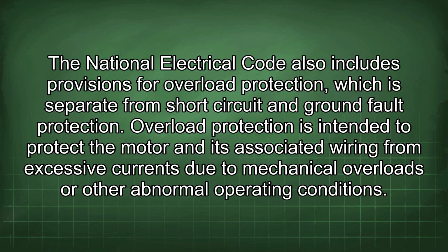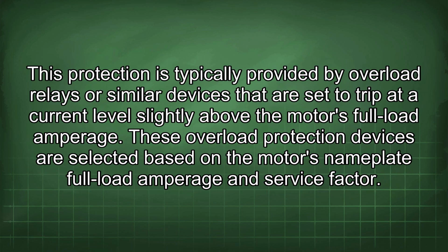The National Electrical Code also includes provisions for overload protection, which is separate from short circuit and ground fault protection. Overload protection is intended to protect the motor and its associated wiring from excessive currents due to mechanical overloads or other abnormal operating conditions. This protection is typically provided by overload relays or similar devices that are set to trip at a current level slightly above the motor's full load amperage.